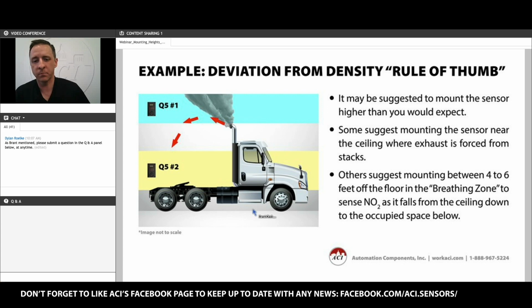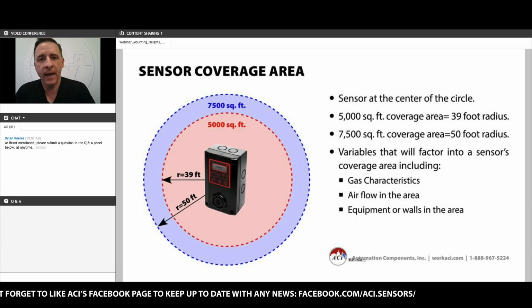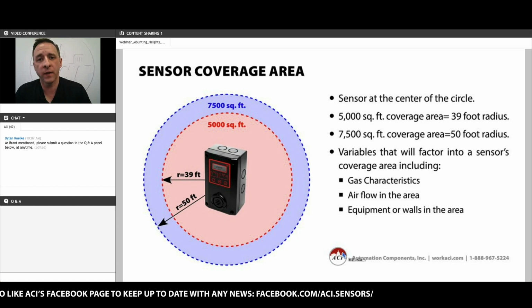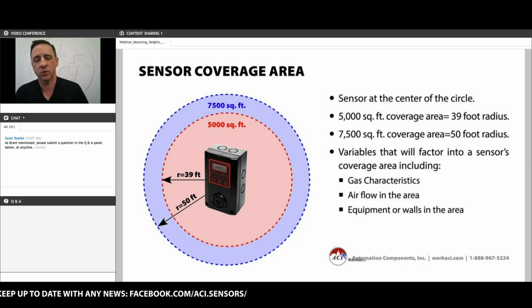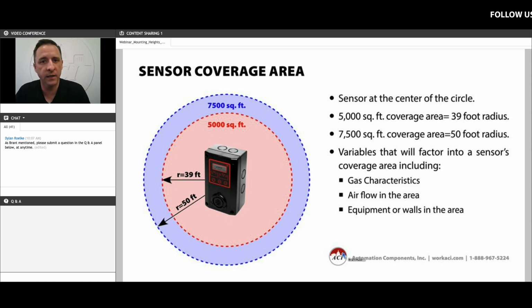Moving on to the placement of gas sensors, depending on the specific sensing element, the type of sensor that's being used, as well as the specific gas being sensed, most gas sensors have an approximate coverage area of either 5,000 or 7,500 square feet. We recommend that you mount the sensor in the middle of that circle, if you will, in order to maximize the coverage area. A 5,000 square foot circle will have a radius of about 39 feet, and a 7,500 square foot circle will have a radius of about 50 feet.